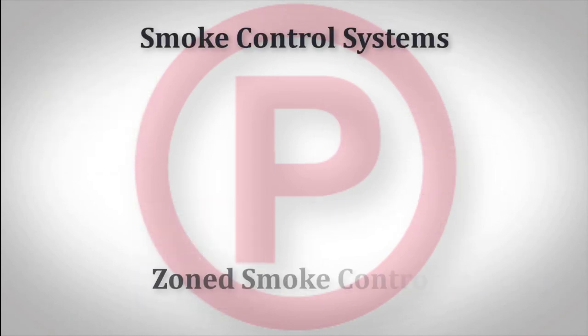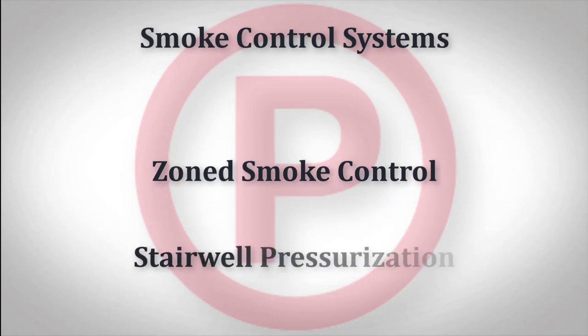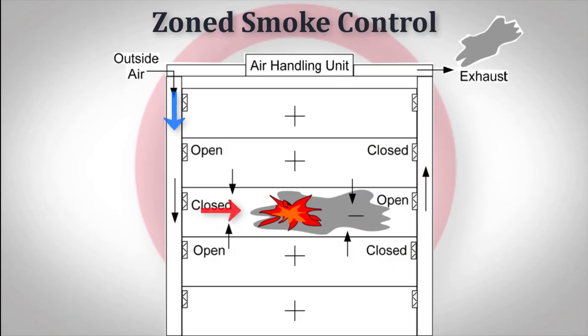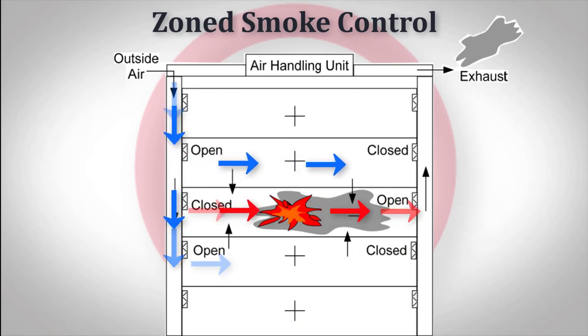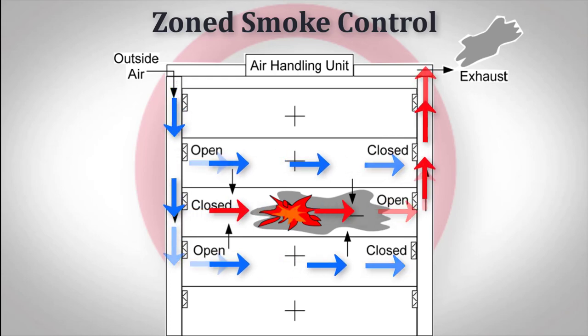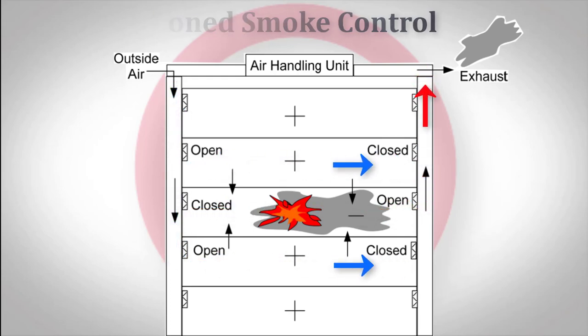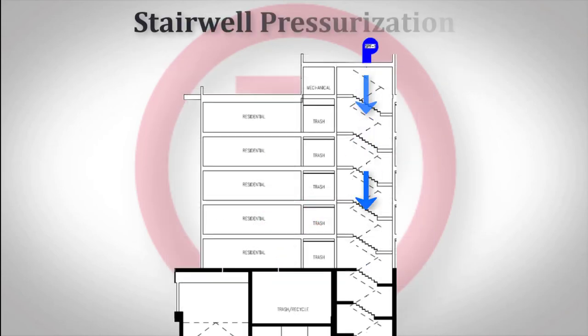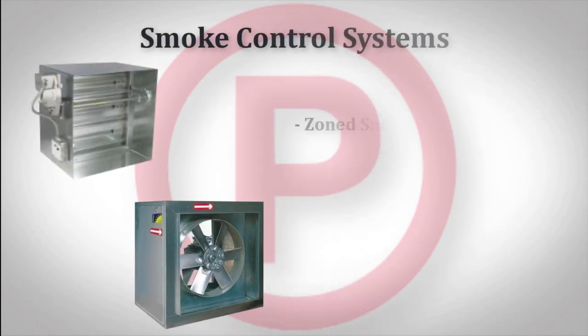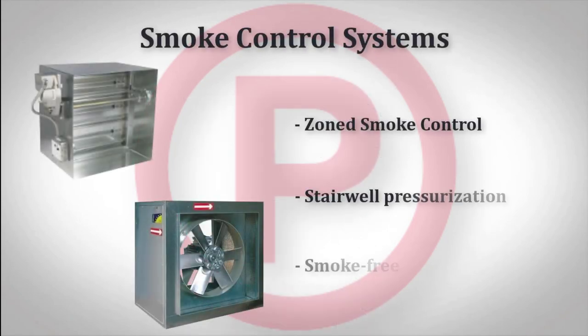Two of the most common configurations you will see are zone smoke control and stairwell pressurization. Zone smoke control is accomplished by exhausting smoke from the fire floor. The floors above and below the fire floor are then pressurized to prevent smoke migration to those areas. Stairwell pressurization is accomplished by simply pressurizing the stairwell to prevent smoke from entering it. The purpose of either configuration is to provide a smoke-free evacuation path during a fire.